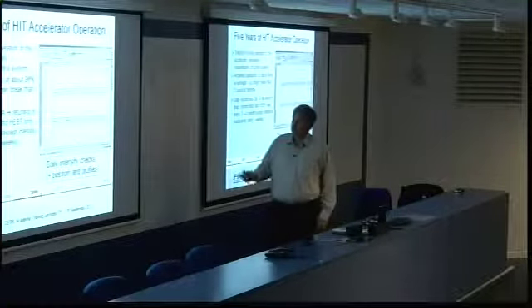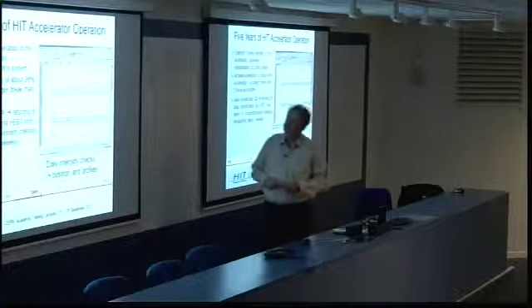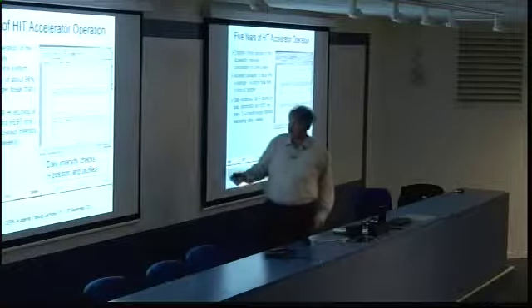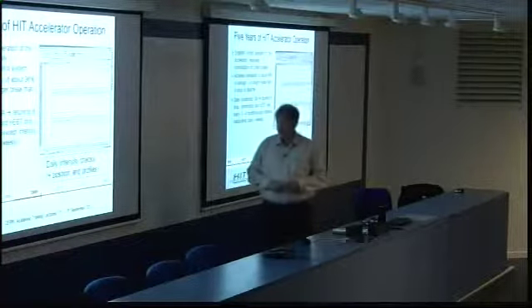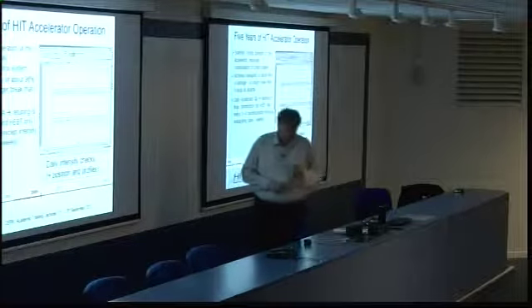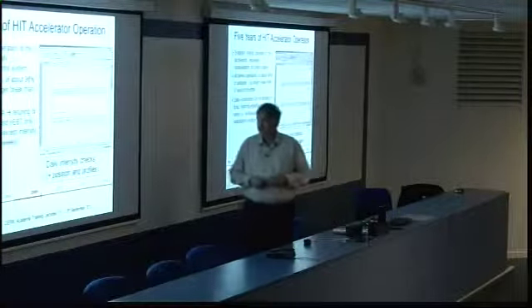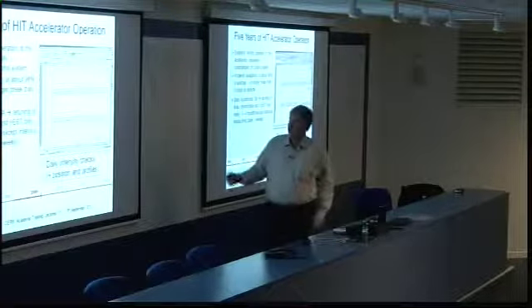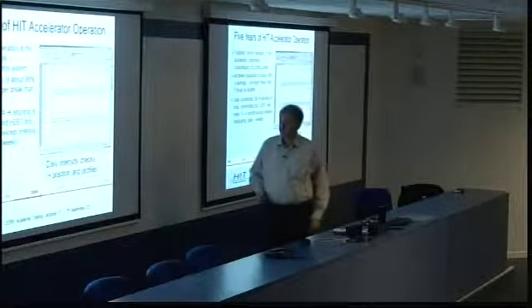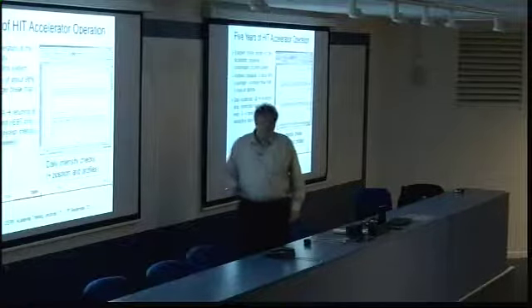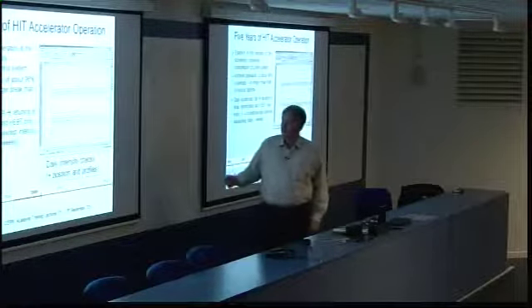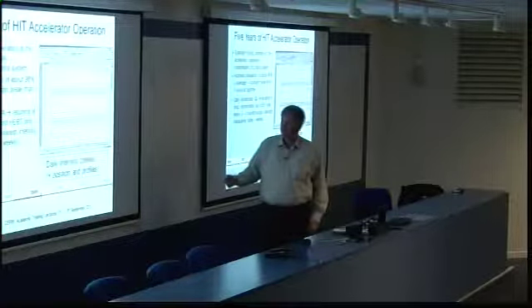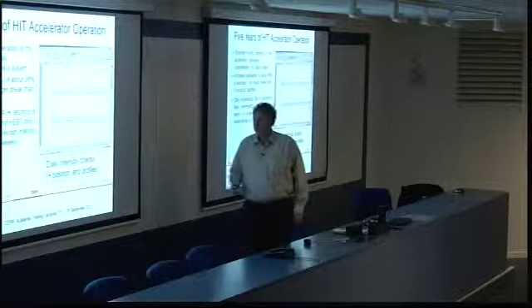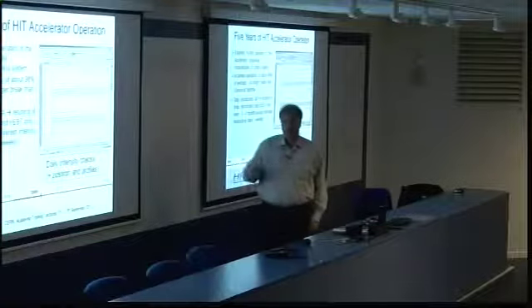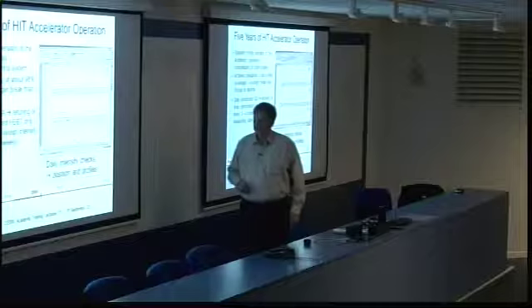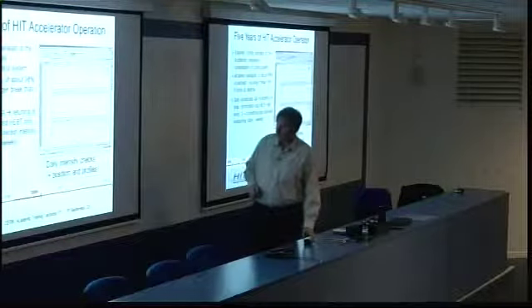And what we found after some months of operation is that retuning of the LINAC, the synchrotron, and the high energy beam transfer line must be done only every 3 to 4 months. Only the intensity from the ion sources had to be readjusted, sometimes daily, sometimes weekly. So it depends. After maintenance days, you have to readjust the intensity daily in the first 3-4 days, and then the intervals get bigger and bigger.